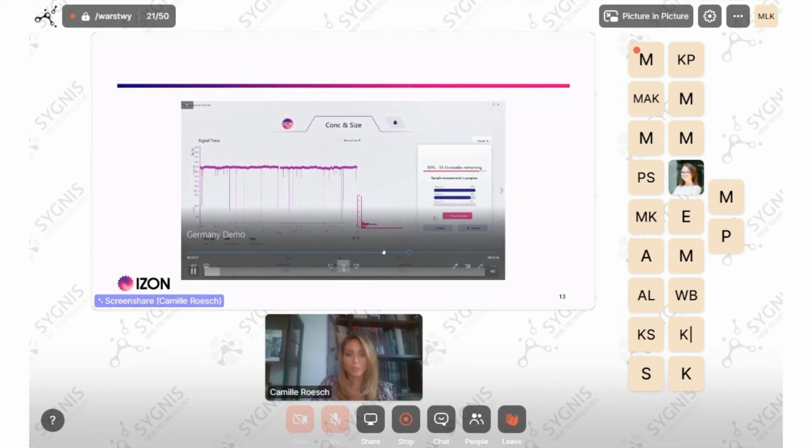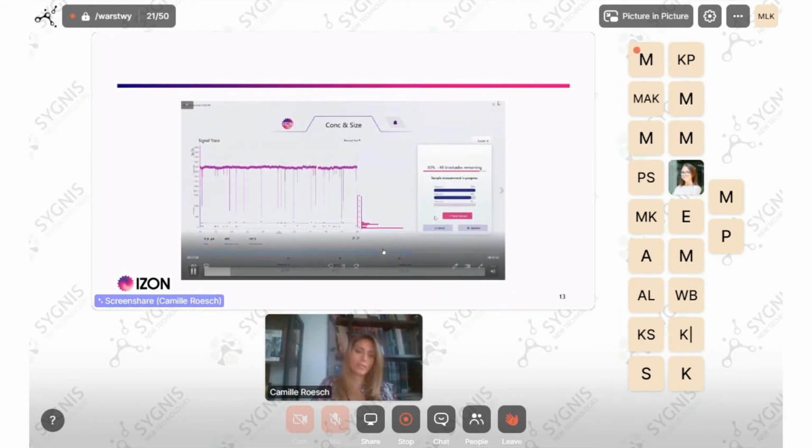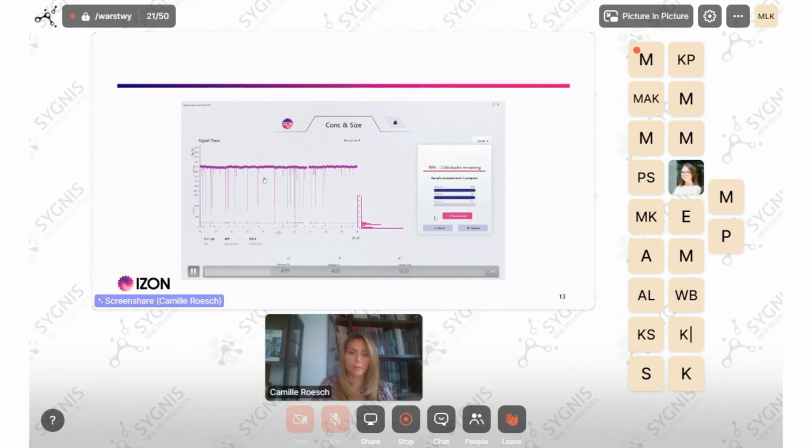So moving on to the actual sample, because previously that was the calibration. Similarly, like the calibration, you're actually having a bimodal sample. You do see that thanks to the size of the peaks: the bigger peaks are bigger particles, smaller peaks are smaller particles. If you take a look at there, you would see that you would have different sizes matching the different peak sizes.